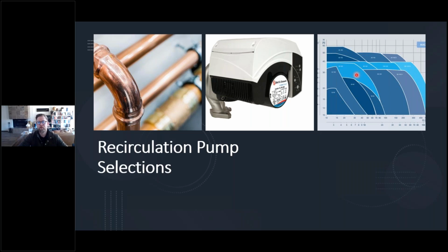Now, a popular collection of pumps recently is variable speed recirculating pumps. The ASPE General Design Guide came up with recommendations to not put them on VFD control, but to have them as a constant flow and head, because the temperature in the system shouldn't be modulating all that much, and your flow and head shouldn't be modulating that much, other than when the system changes from closed to open. If you're sizing it correctly, the thinking went that you should be in a pretty fine-tuned area.